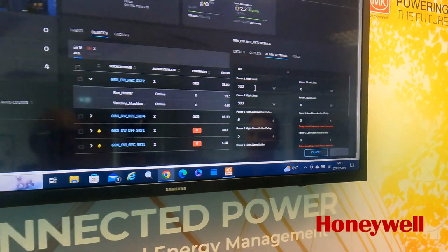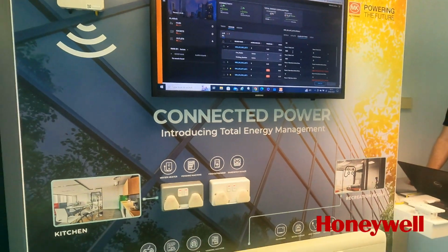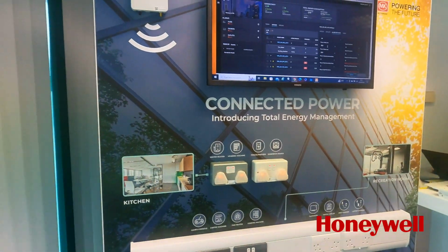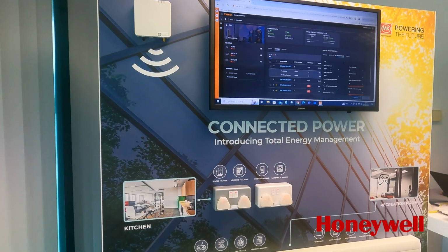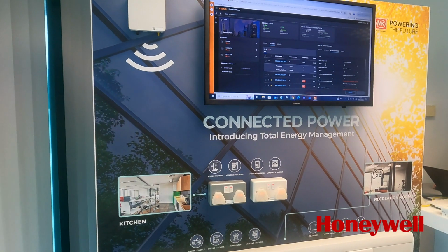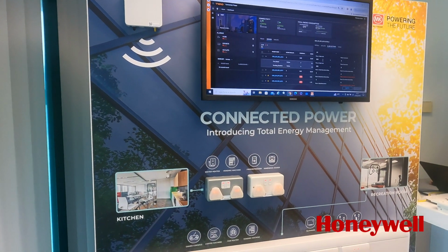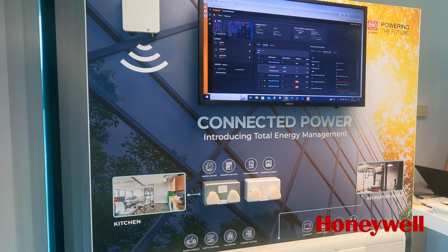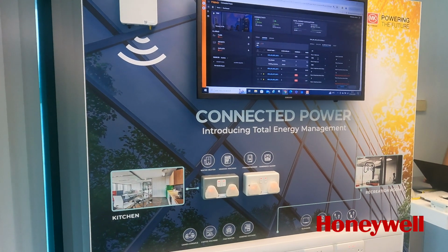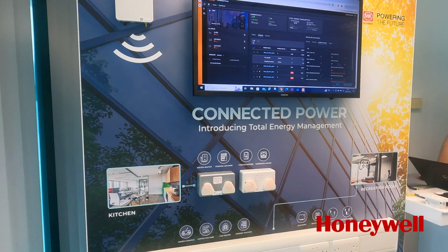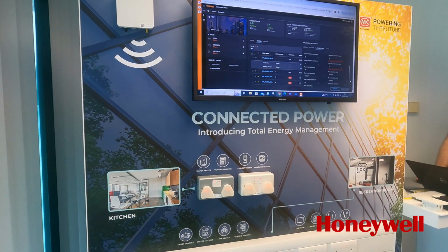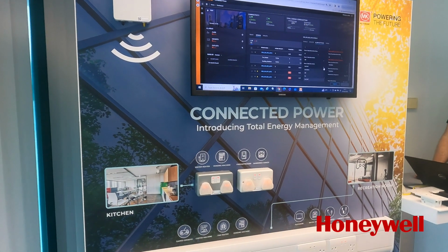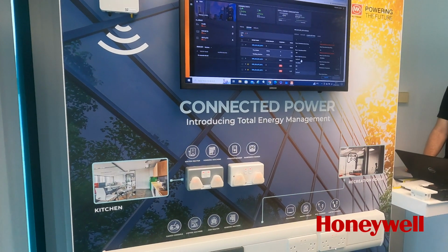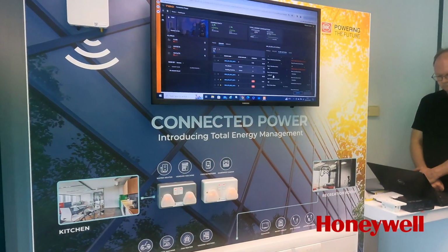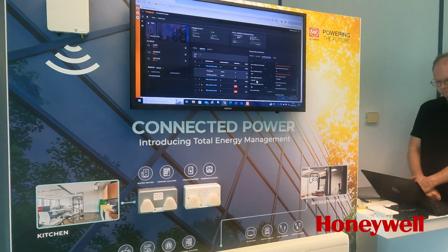That will just send an alarm directly through to our BMS. That can be as an email as well, or as a text message. But we can also use that alarm to trigger an event, which can automatically turn the socket off. If you wanted to, it can also automatically lock the socket off, as we have got here, so it's already set up to lock off if it goes over 500 watts.